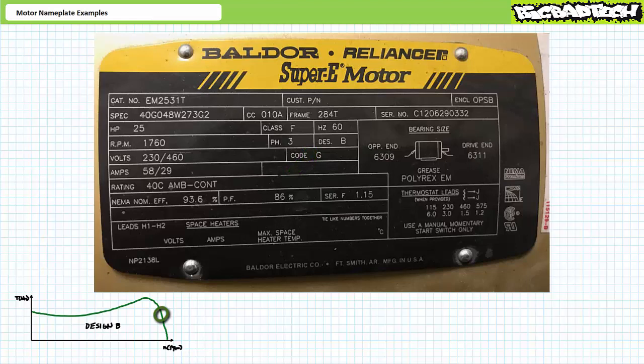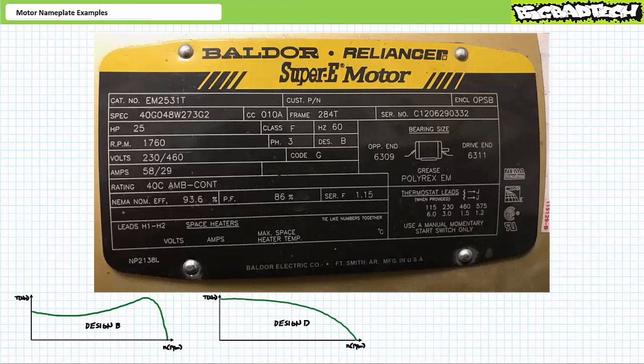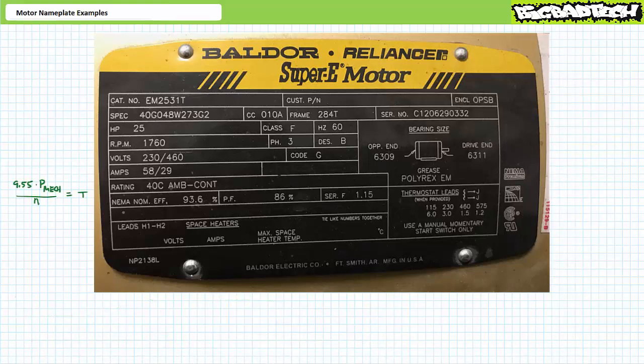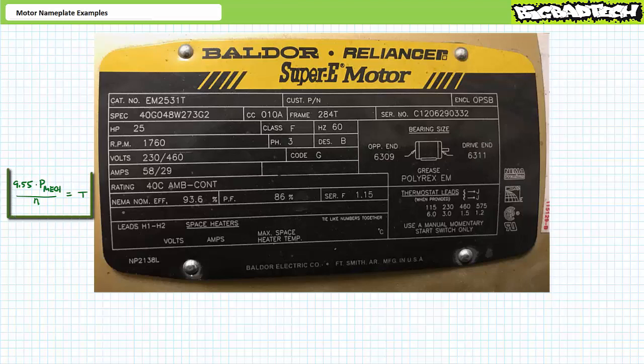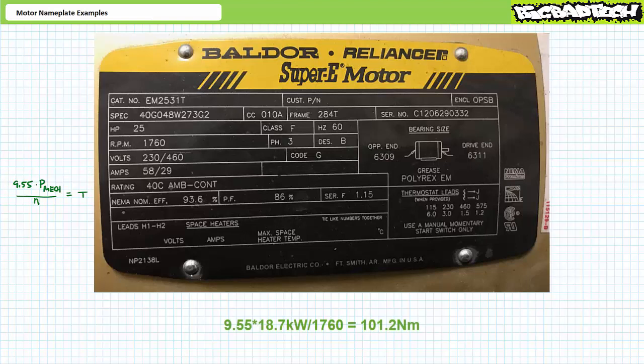At the rated condition, the motor turns at rated speed and produces its rated torque. At less than rated condition the motor will speed up; at more than rated condition it will slow down. Anything to the right of the rated condition is an under-load; anything to the left is an overload and isn't meant to be sustained. NEMA Design B motors are general purpose induction motors, whereas NEMA Design D motors are for high torque, low speed applications. The rated torque isn't specified on this nameplate, but we can back-calculate it: torque = mechanical power × 9.55 ÷ rotational speed, giving approximately 101.2 newton-meters at rated condition.